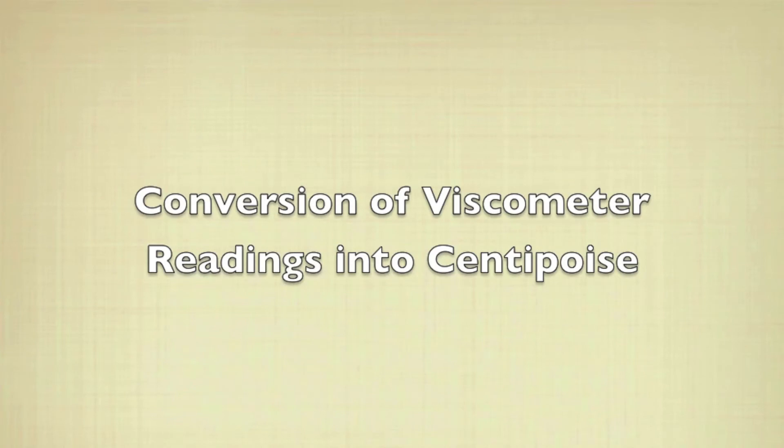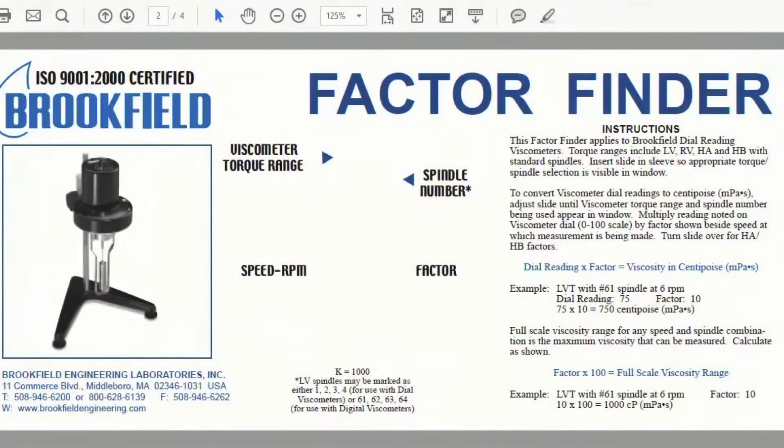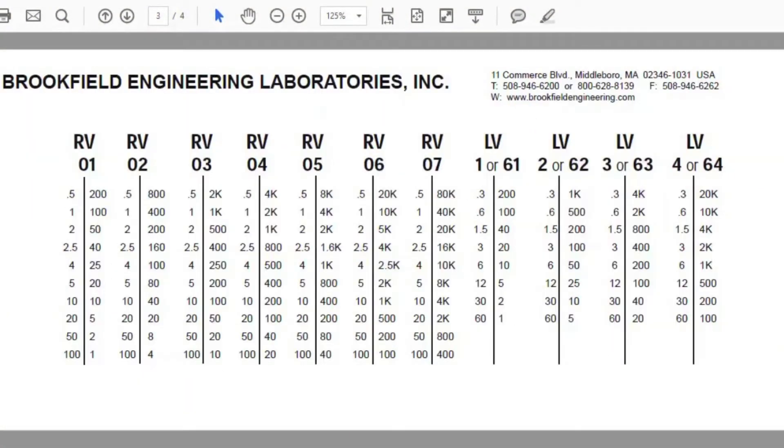To convert the viscometer readings into centipoise, the Factor Finder PDF from Brookfield Engineering can be used. This PDF comes with an array of conversion charts.